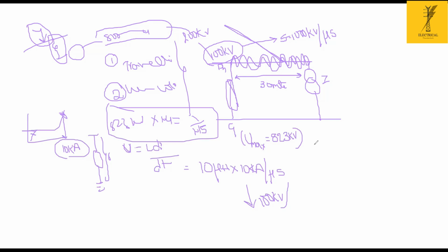Instantaneously, when a fault occurs and 823 kilovolts appears in the system, some energy appears on your lightning arrestor during a single discharge, and it is not allowed to exceed the metal oxide resistor thermomechanical overstress limits.